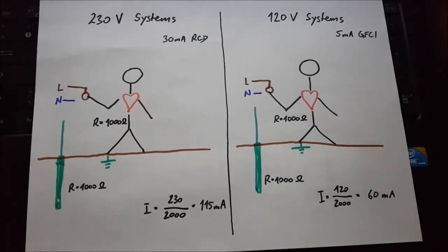So as you can see, in both cases, the RCD tripping current is always much, much lower than the actual current which will actually occur. It is not the value of the leakage current which is protecting the human most. What is protecting the human is how fast the RCD or the GFCI is disconnecting the circuit.